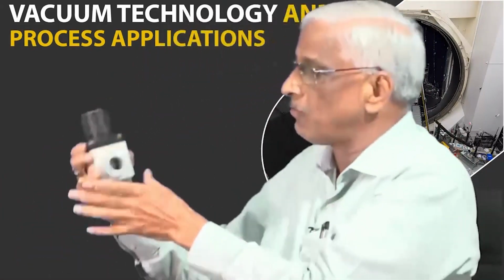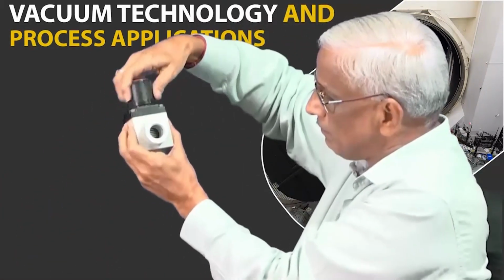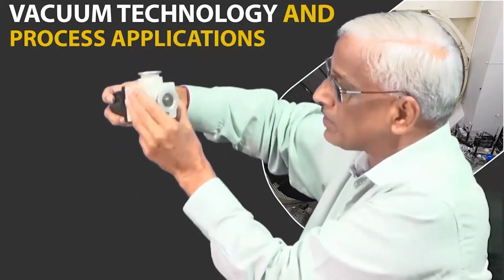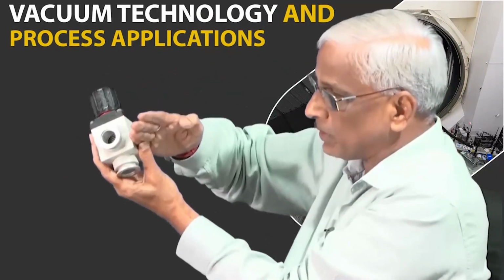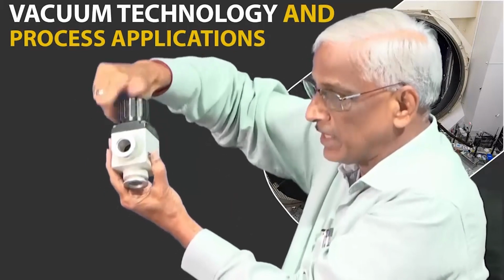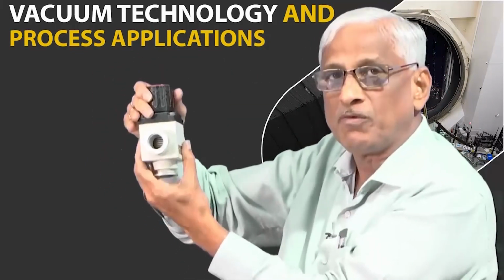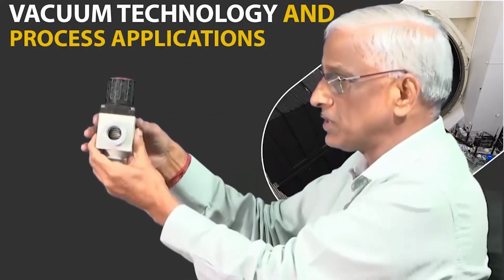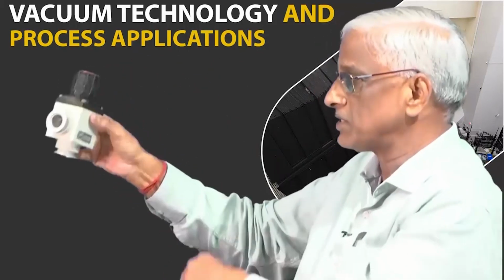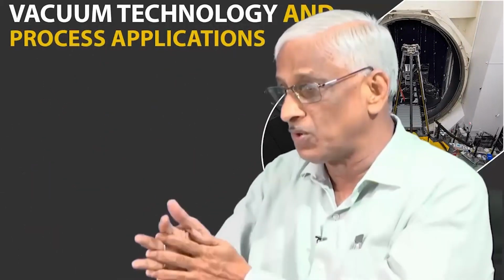And these are right angle valves with bellow inside. When I try to do this in a manual operation, it opens up the bottom seal and it gets engaged. It is a beautiful way of isolating 2 chambers at minus 5 torr type of things. But at minus 7, minus 8 when you go, you have to use all metal valves.